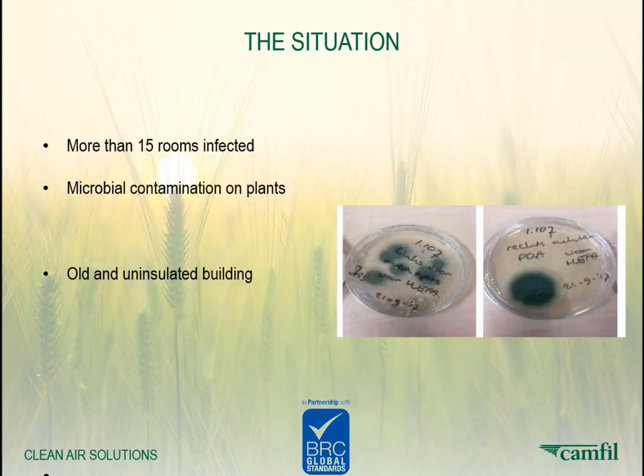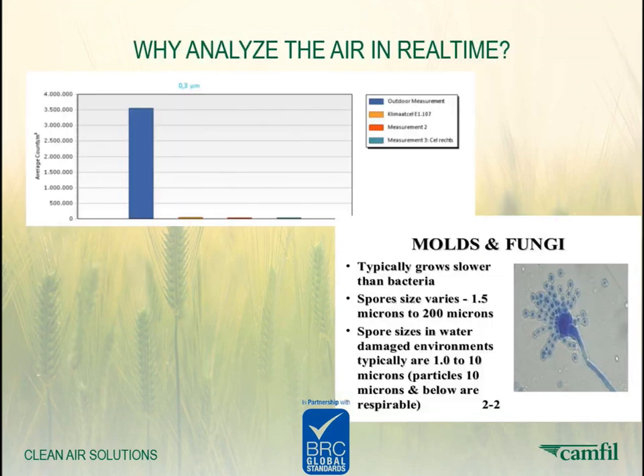The situation at the research center was microbial contamination in 15 climate rooms for plant breeding. In the picture to the right, we see agar plate samples from the rooms. The result is in CFU, a colony forming unit. This is a unit used to estimate the number of viable bacteria or fungal cells in an air sample. We analyzed the number of particles per cubic meter in real time, and the diagram shows the count of particles by particle size. CFU samples for mold and fungi were also taken. Molds and fungi typically grow slower than bacteria. The spores have a size between 1.5 and 200 microns. Abnormal values of spores are often possible to detect during particle counting in real time.